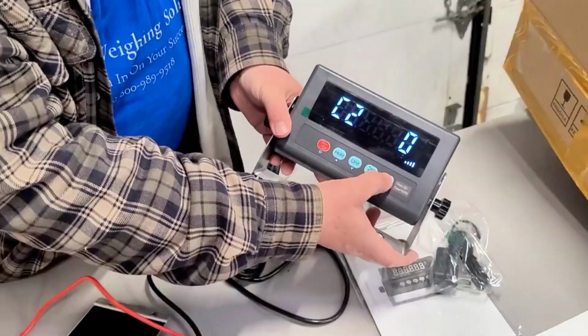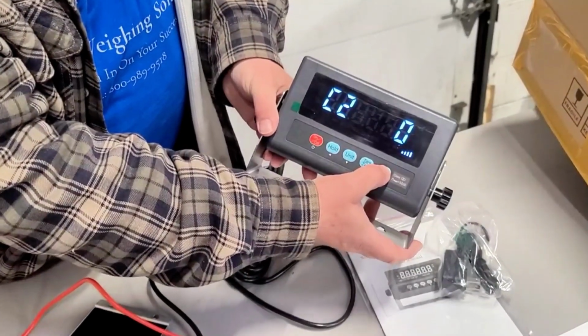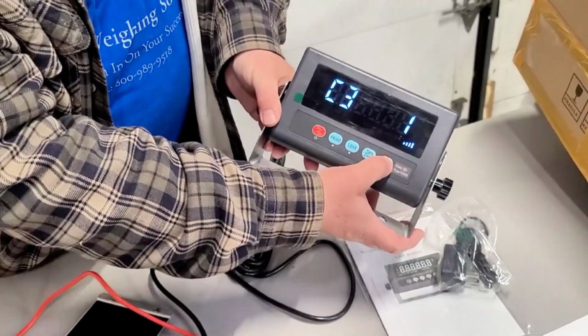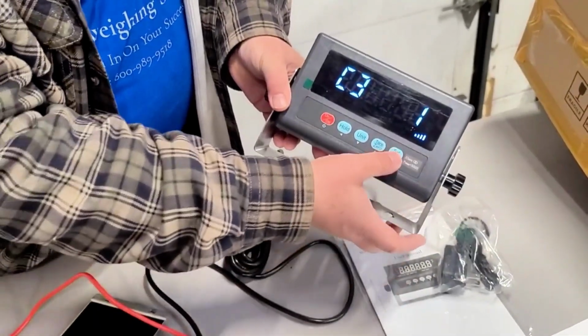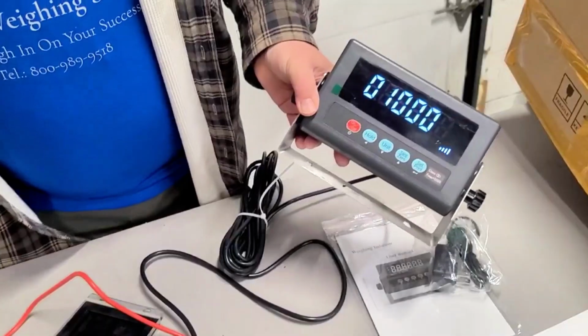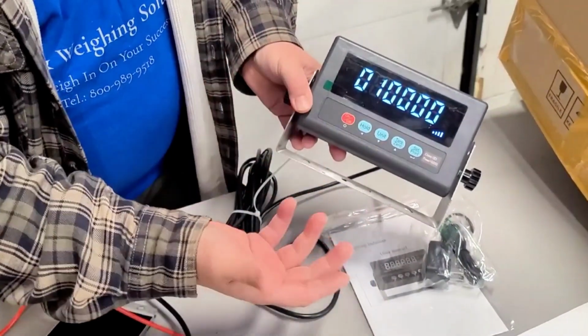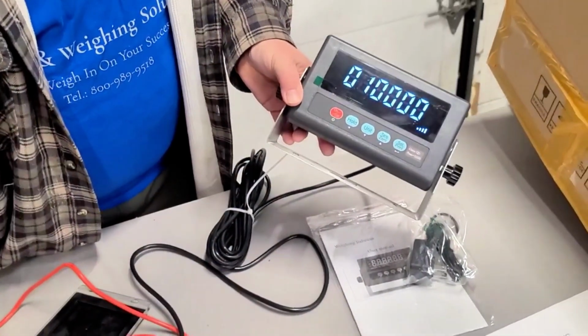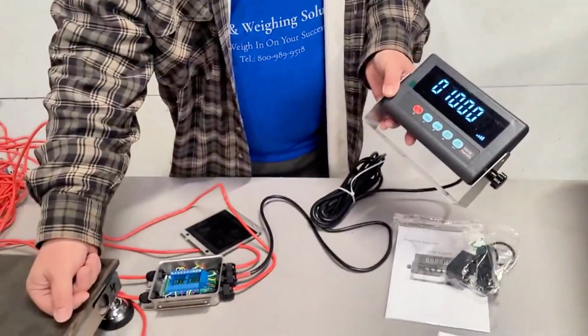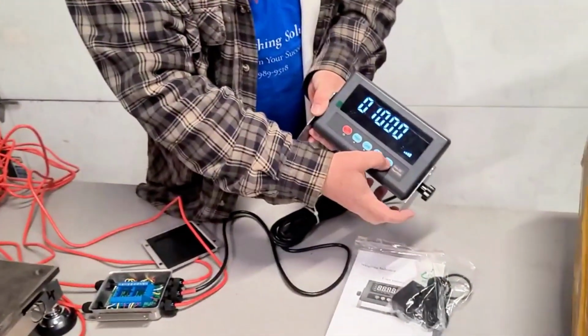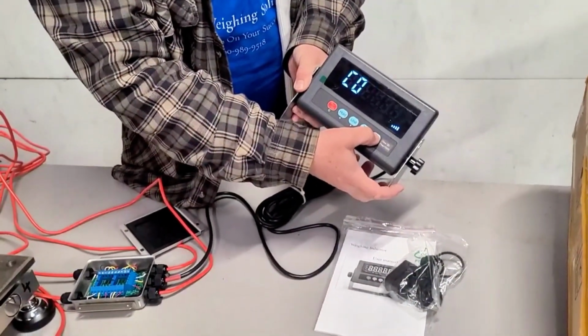C2 is going to be, we're not going to have any decimal point because we're going to weigh by 1 pound. C3 is going to be, we're weighing by 1 pound, so in 1 pound increment, that's going to be at 1. Number 4 is going to be our full scale capacity. We have a 5,000 pound load cell, so for that, we're going to use 10,000 pound. You could use it also for a hopper because the material enters from the top. We could use this for 20,000 pound. Now we keep it at 10,000 pound since we have a small base.